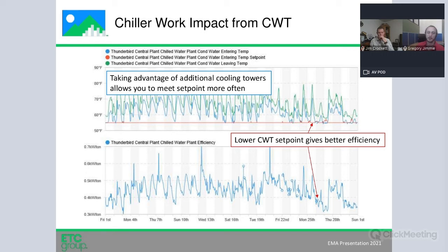is exhibiting. And just to give you a visual to think of, if you were to say your set point was at 70 degrees, that would be somewhere up in here, and that would effectively sit your best operating point closer to 0.5 kW per ton. So now, because we're driving it down to 58, that's the difference in efficiency gains. So now, instead of staying up closer here to 0.45 or 0.5 kW per ton, now we're talking 0.35 or 0.4 on those same points, or under those same conditions. So you can drive that condensing water lower than I think most people would think.